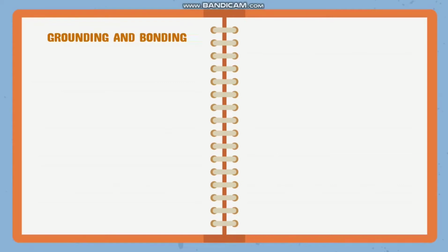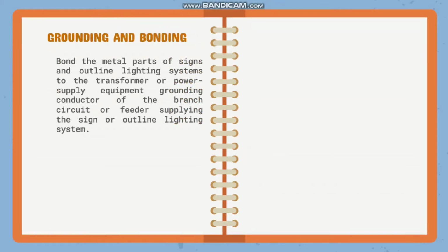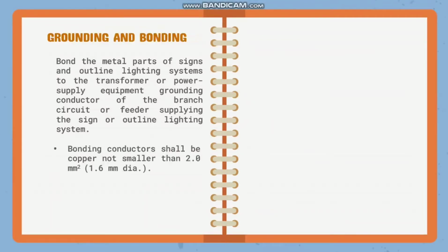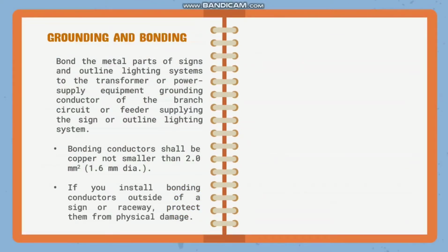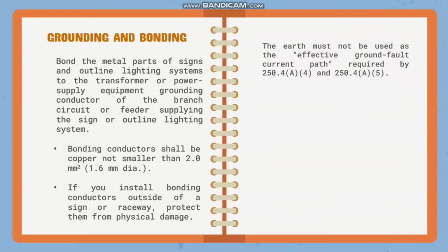Next, grounding and bonding. Bond the metal parts of signs and outline lighting systems to the transformer or power supply equipment grounding conductor of the branch circuit or feeder supplying the sign or outline lighting system. Bonding conductor shall be copper not smaller than 2.0 mm squared or 1.6 mm dia. If you install bonding conductors outside of a sign or raceway, protect them from physical damage. The earth must not be used as the effective ground fault current path required by 250.4A4 and 250.4A5 of the National Electrical Code.